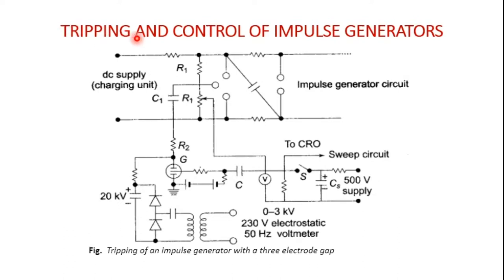Next, we have tripping and control of impulse generators. In large impulse generators, sphere gaps are generally used for the spark gap arrangement, along with gaps formed by hemispherical electrodes. These gaps are arranged so that sparking of one gap results in automatic sparking of another whenever voltage is impressed on it. For consistency in sparking, UV light irradiation is provided from the bottom of all the spark gaps.